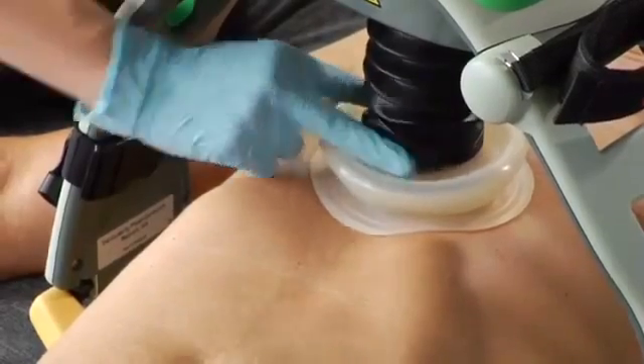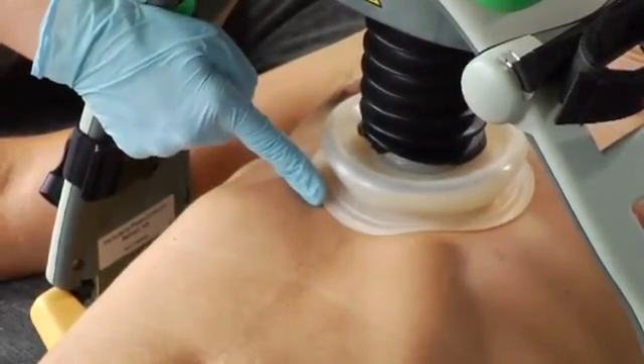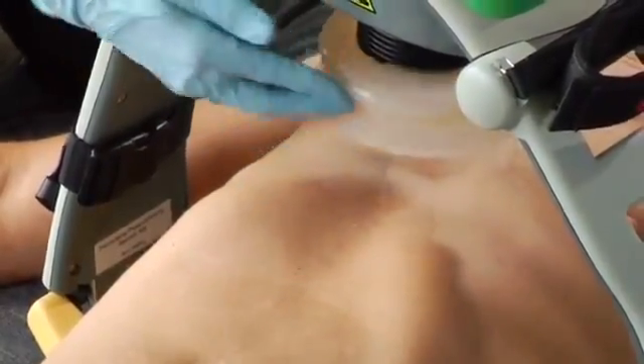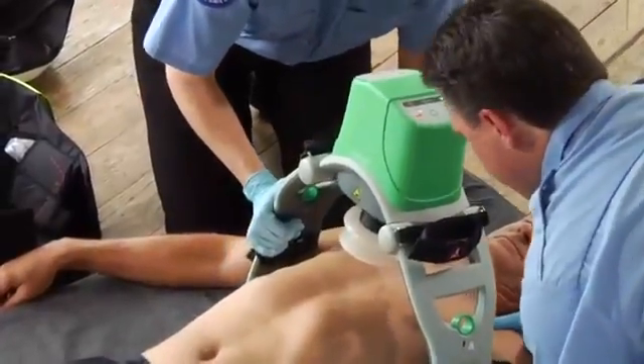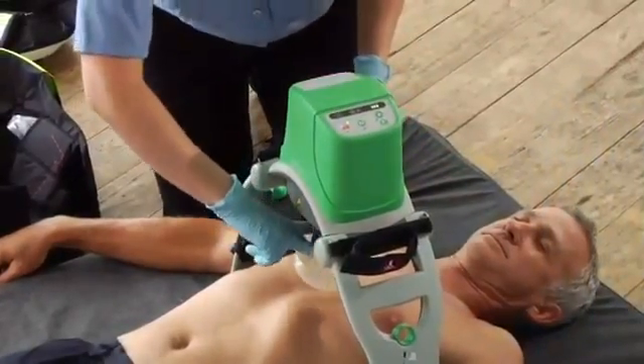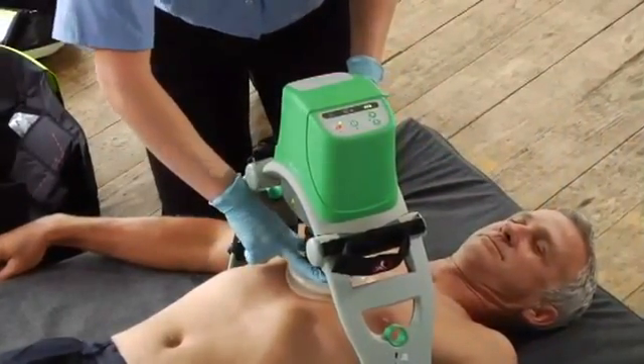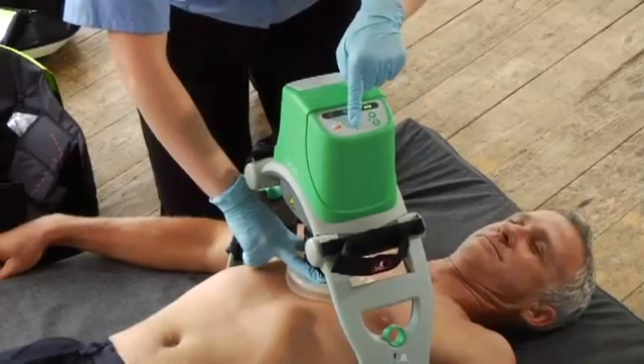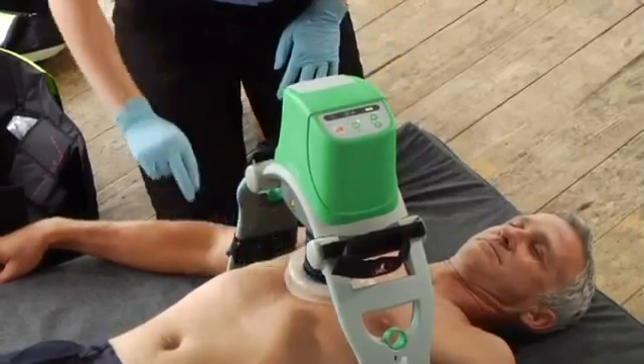If the edge of the cup is a bit below the edge of the sternum, you'll have to reposition. Lift it back up and move Lucas by pulling on the support legs. Push the suction cup back down and reposition. Hold it there and push the pause button to set the upper limit of compression. Now you can take your fingers off the cup. It's important to press the pause button before removing your hand from the suction cup.